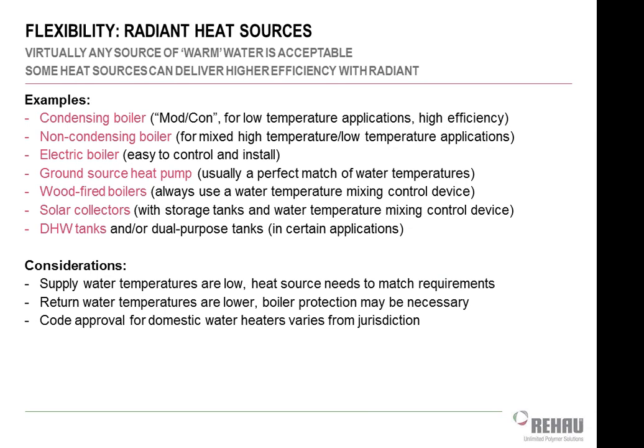So we haven't done a radiant system in our building, in our office here, for probably at least 12 years that didn't have a condensing boiler on it. The old cast iron boilers with a mixing valve and all that, that's all gone these days. Everybody who does radiant would use a condensing boiler as opposed to a non-condensing boiler, because we can set the water temperature for whatever we want, tell it to give us 95-degree water or something like that, and it works perfectly well.